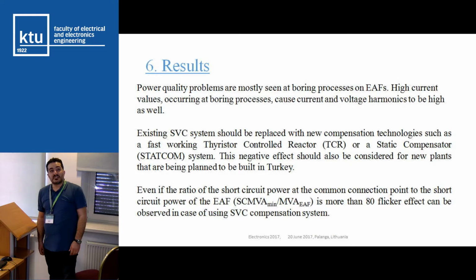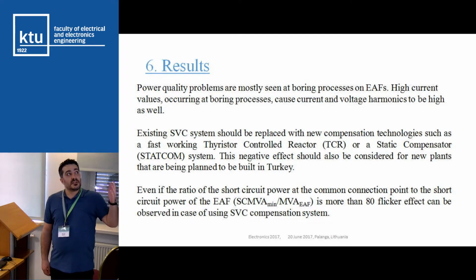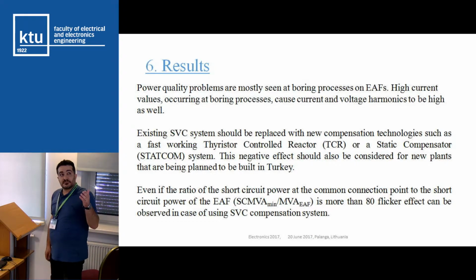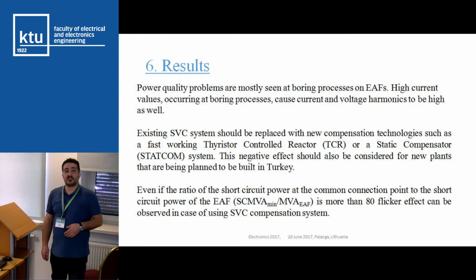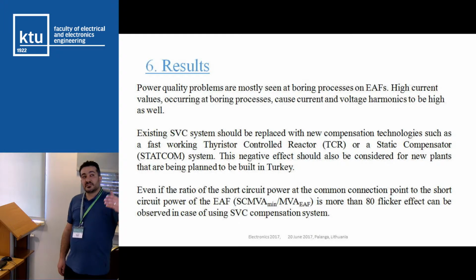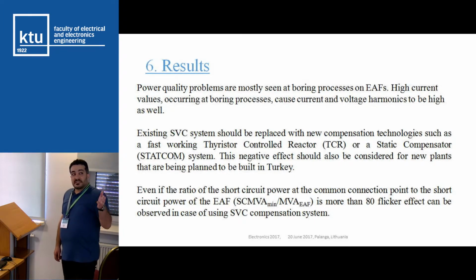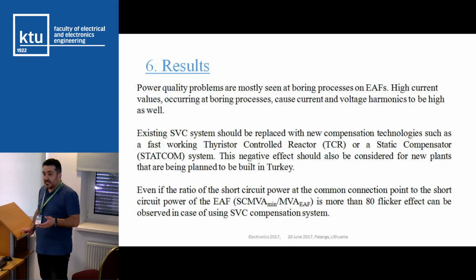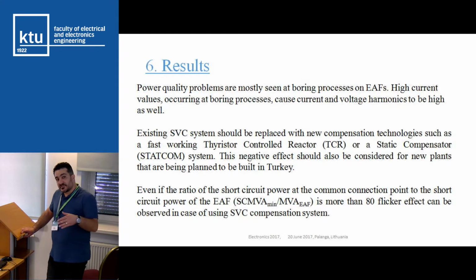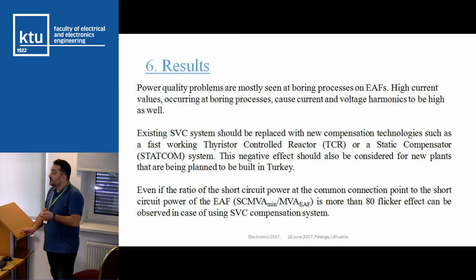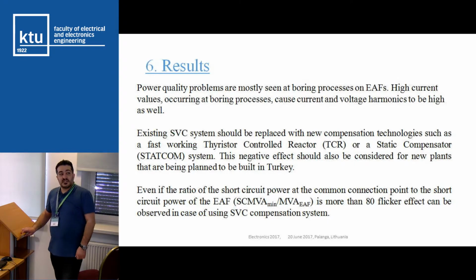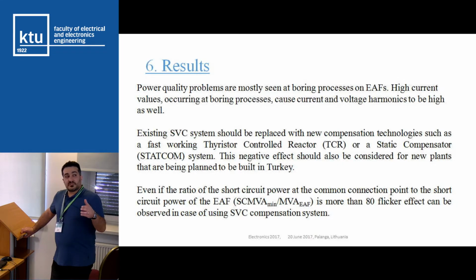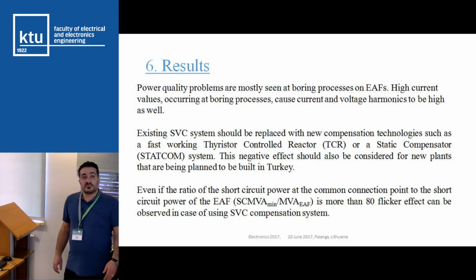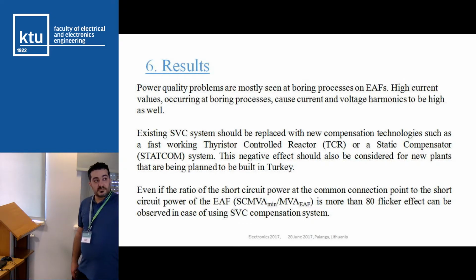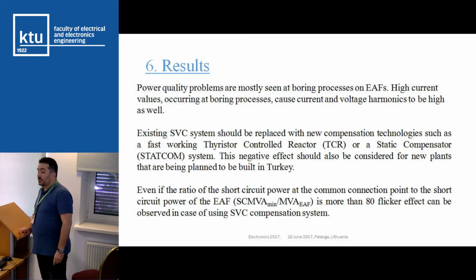As a result, we can say that power quality problems are mostly seen in the boring process of the electrical arc furnace, and high current values occur in this process. The existing SVC system is not suitable for electric arc furnace application, because we see experimentally that the SVC system causes even harmonics, and even harmonics are a problem for us. We suggest that, instead of SVC systems, a thyristor controlled reactor or STATCOM systems be used.